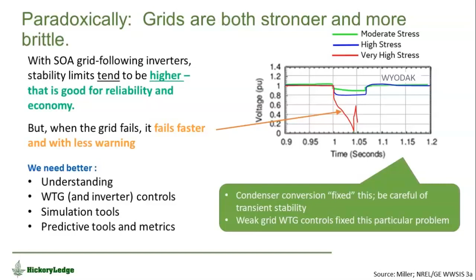But the third thing that's really important is that, and I come back to this, this system would have been unstable long before, had it been the equivalent with synchronous machines. The system is pushing more power than it could have with standard synchronous machines. So let's go on.